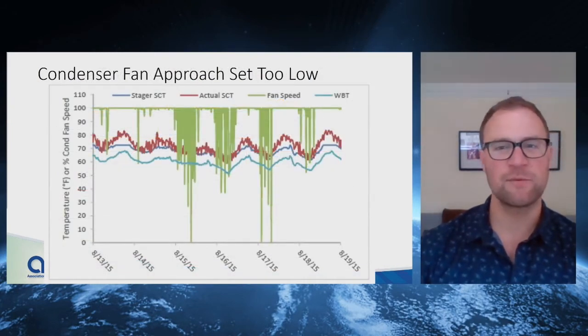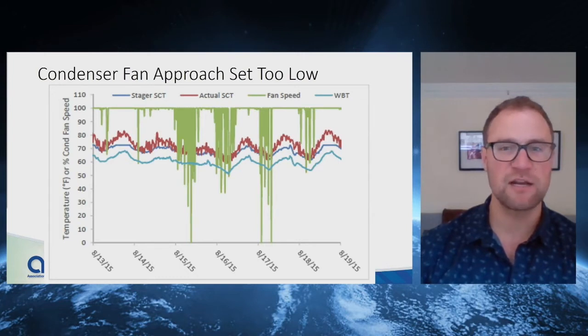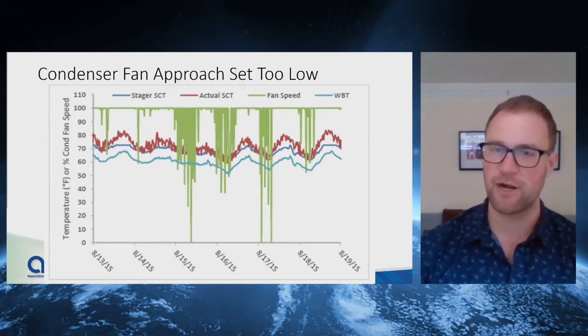This one is actually pretty similar to the last example. It's a refrigeration system where the approach temperature, again, was just set unrealistically low. The light blue line on the bottom is the outdoor ambient wet bulb. The dark blue line above it is what the control system is calculating the condensing temperature should be, based on the approach temp that was programmed, right?